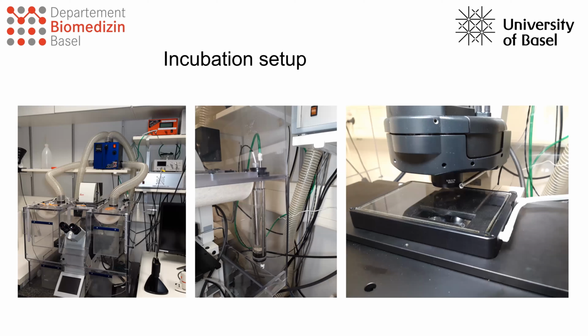On this slide, you can see how a standard live imaging setup looks in our facility. So we also have these incubation boxes around the microscope. We actually have this heater on top of the shelf, and then we heat up the whole microscope. The advantage here compared to a stage top incubator is that the whole system is at 37 degrees. And that also allows you to compensate a little bit for temperature drifts within the room if your ventilation goes on, or if your air condition kicks in. Also overnight, sometimes they are reduced during off hours, and then we might have slight temperature changes in the room. So this actually keeps the whole system stable.